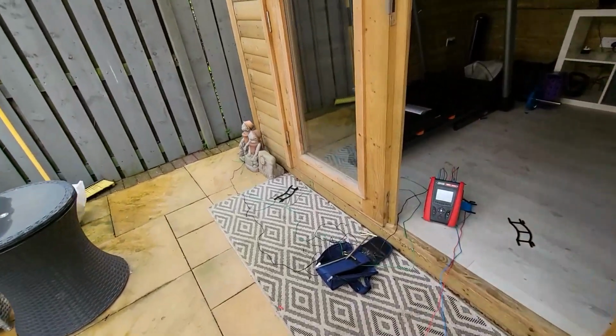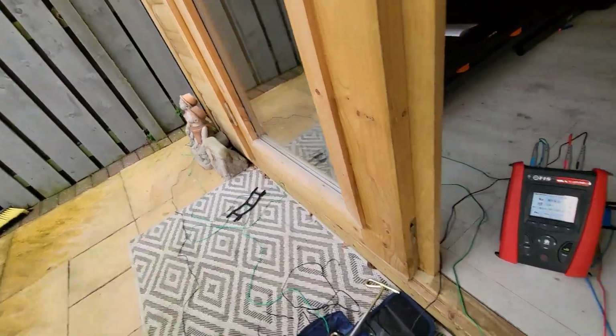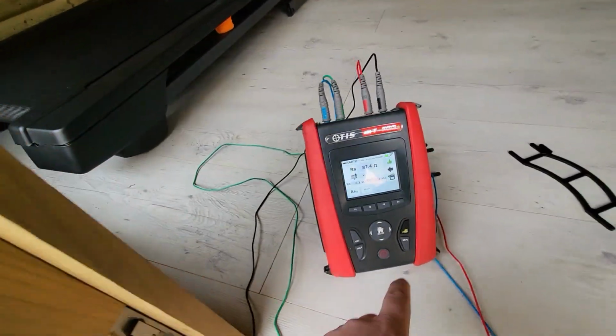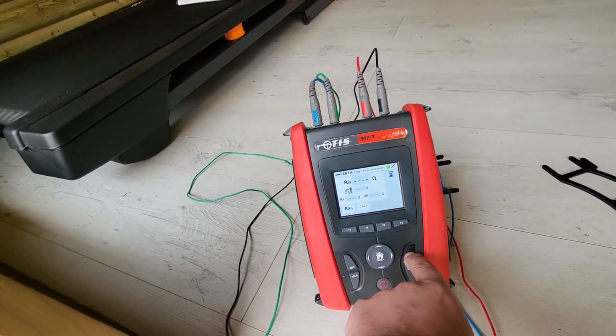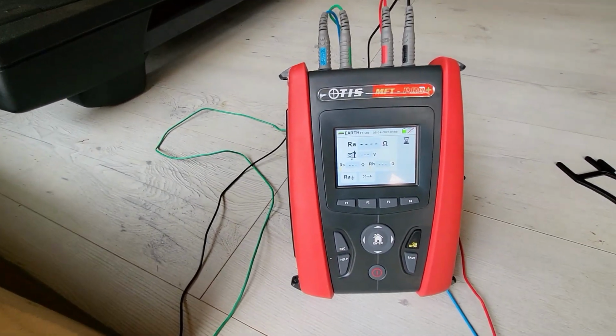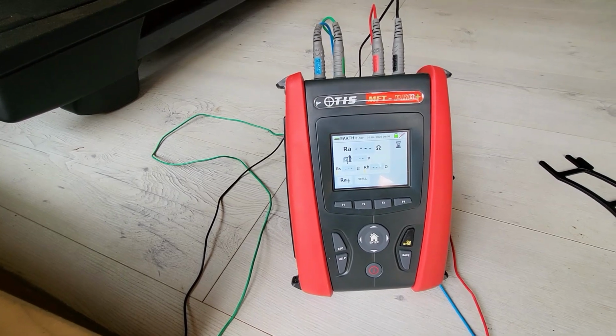So the black and the greens, again, as you'll have seen on that picture, are still going off to the earth electrode, and we can hit test. I'll leave it on the TT setting, it still carries out the test in the same way.